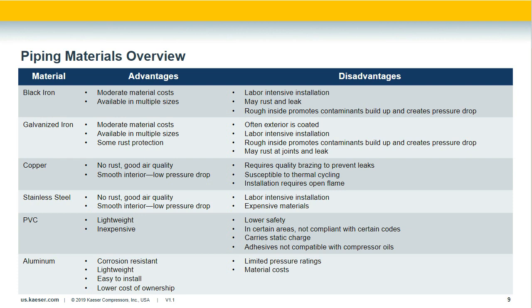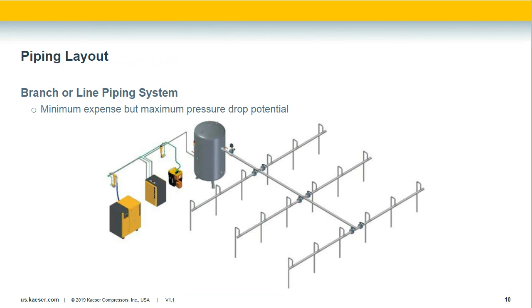Now let's talk about piping layouts. With a branch or line piping system, compressed air travels from the compressor room through a main header pipe and branches out to points of use. As you move down the pipe, the longer the run, the more pressure drops at the point of use. It's recommended to maintain a 10% or less pressure drop between the compressor generation and the point of use. Piping can have a huge effect on meeting that number, especially if undersized.